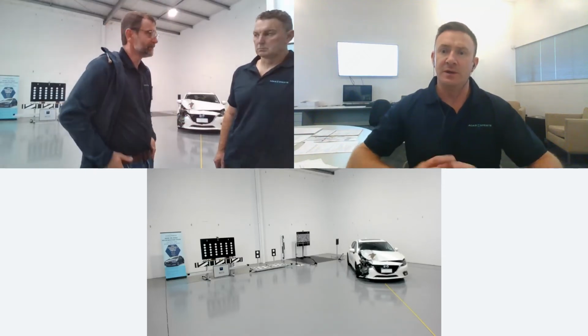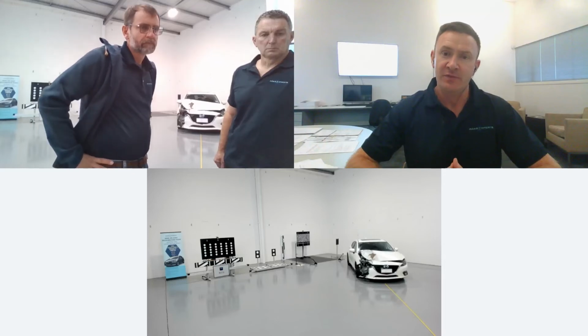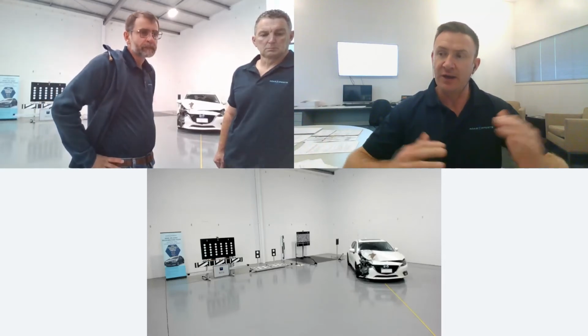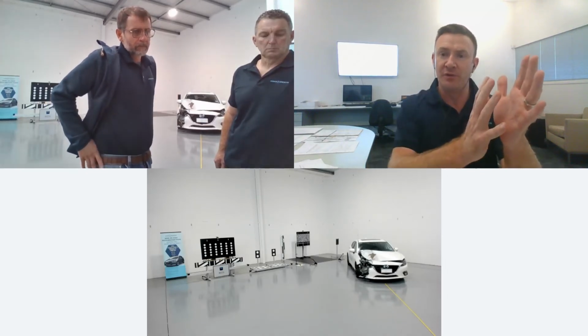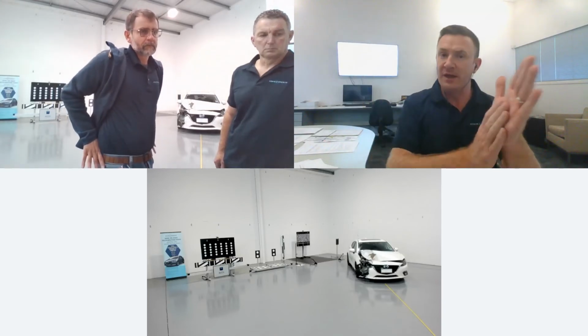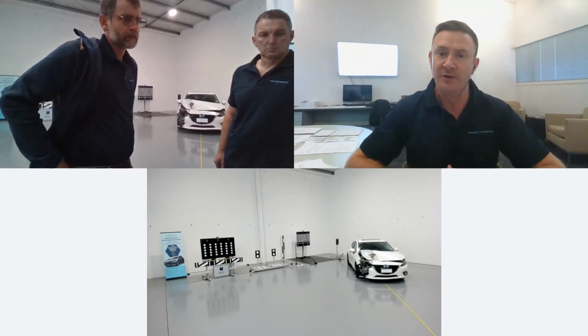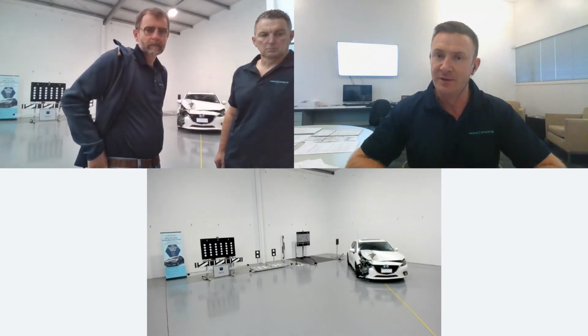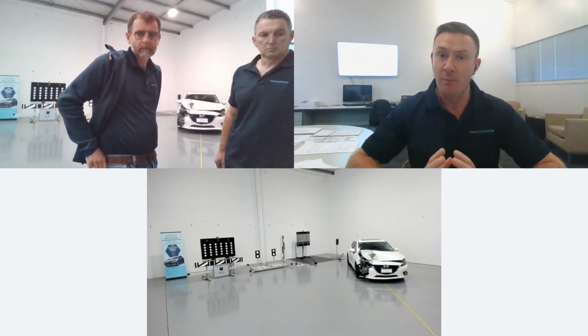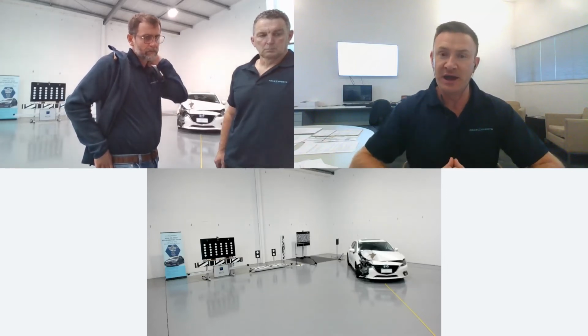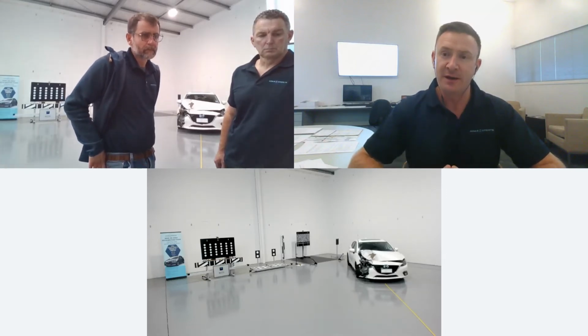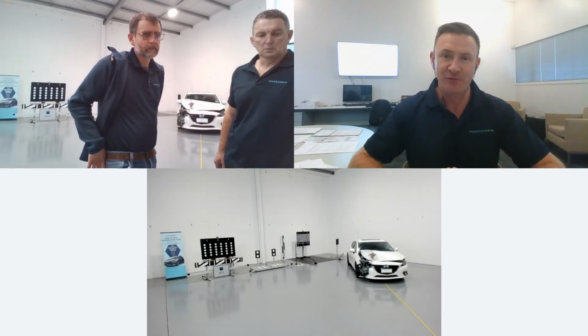Yeah, and I think too, it's probably not the most common type of fault, but certainly some of the most challenging faults are where there are underlying conditions. All these modules work and communicate together, and sometimes you can have a problem present as one thing, but there are other influences causing that to be brought to the fore. So there are a lot of challenges and complexities when you don't get an easy calibration. It doesn't just calibrate off the bat. Then it becomes quite complex to get a result sometimes, or to find the actual culprit causing the problem.